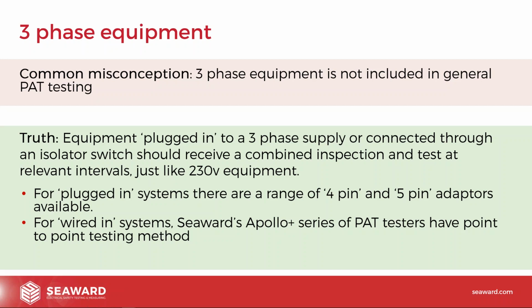Generally, we would do it using adapters. So we'd normally have adapters from 3-pin through to the three-phase plugs, either the 4-pin or 5-pin adapters. Generally, these adapters connect all of the lines and the neutral, if there is one with the 5-pin, together, and then the test would be carried out in a normal way. So it would do the insulation resistance between the earth and all the live conductors joined together, and earth continuity and things like that are done exactly the same. There isn't really any difference to the testing we would carry out, or the visual inspections.